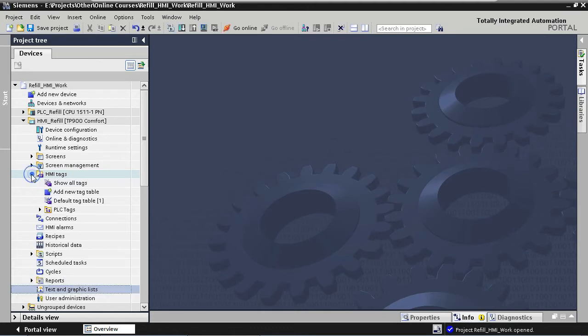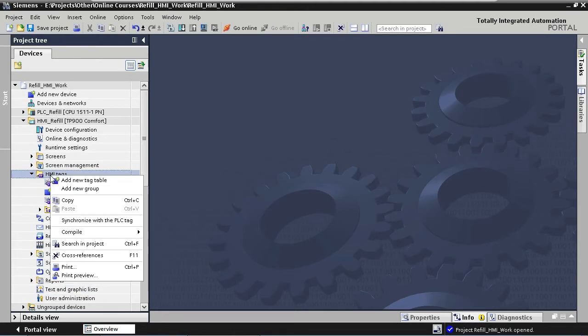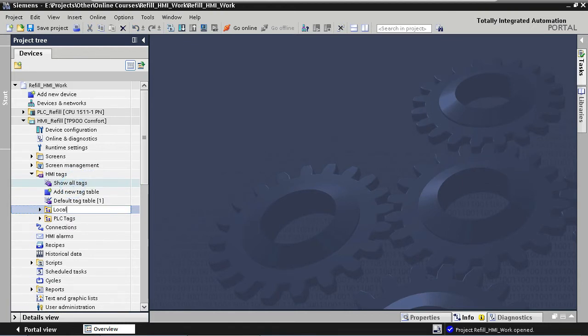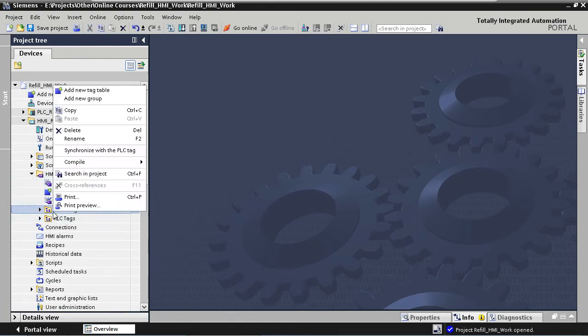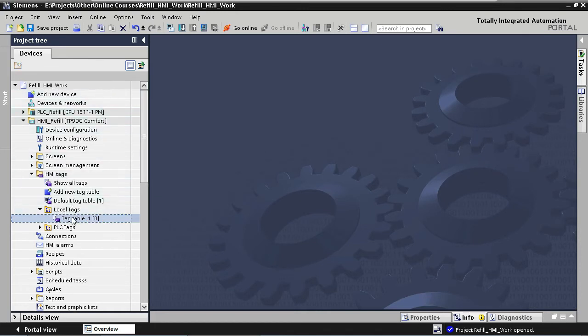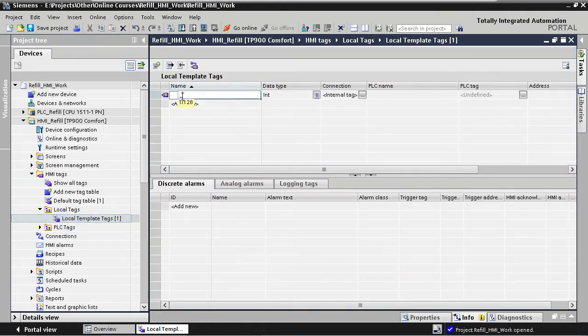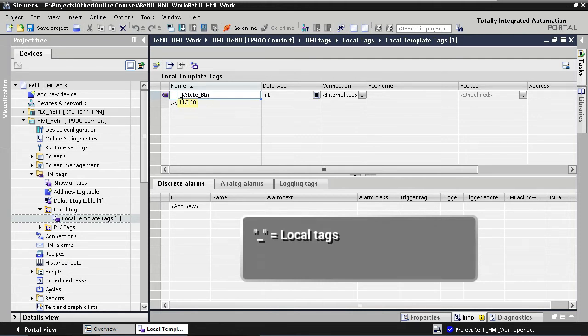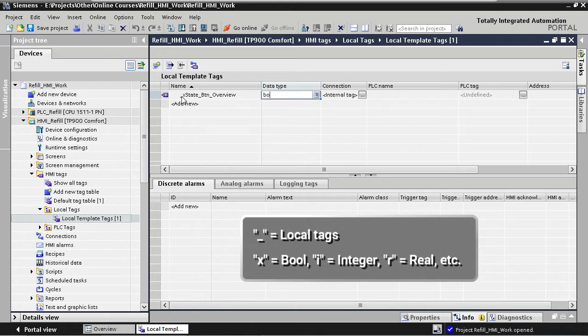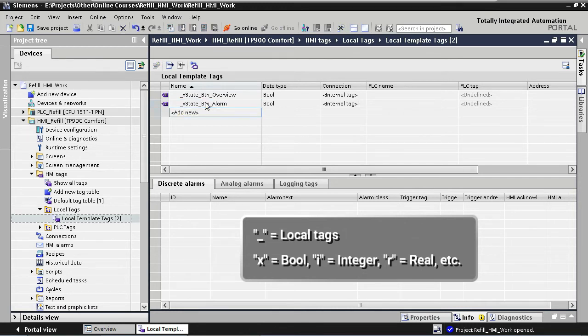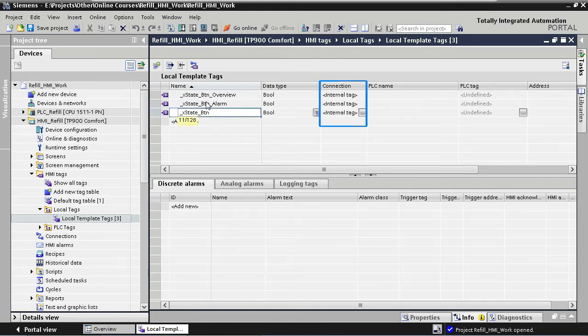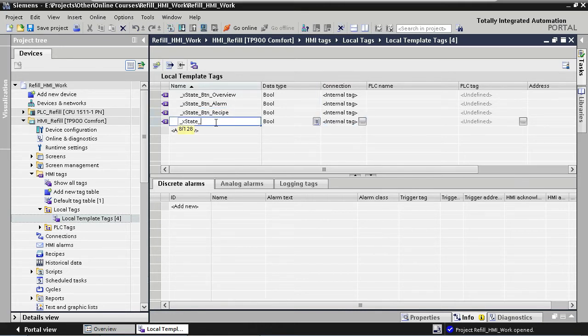Under HMI Tags in the tree structure we start by creating a new tag group called 'Local Tags,' and under this group we create a new tag table called 'Local Template Tags.' We then open the tag table and create four boolean tags. Tag names start with an underscore to indicate they are local tags, and I'm using X in front of the tag names to indicate boolean tags — for integers I would use underscore I, for reals underscore R, and so on. The tag connections are by default set to Internal Tag, meaning these are local HMI tags not synchronized to any PLC tags.